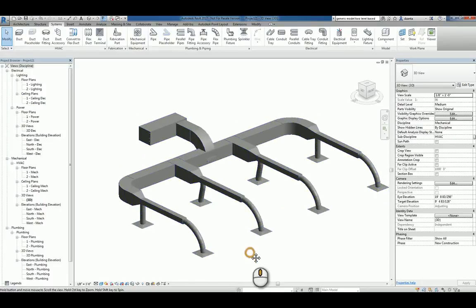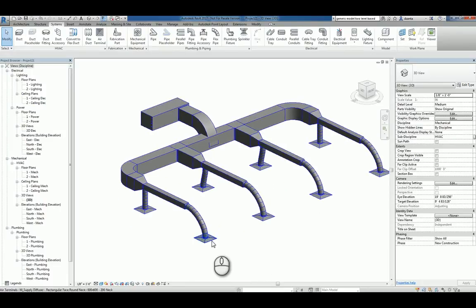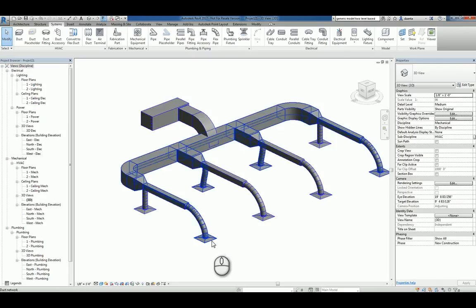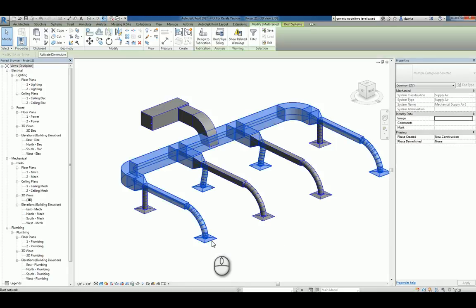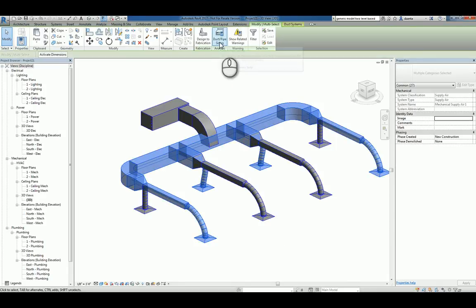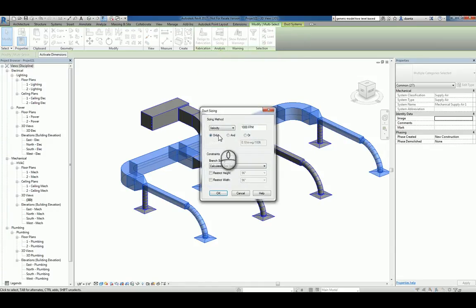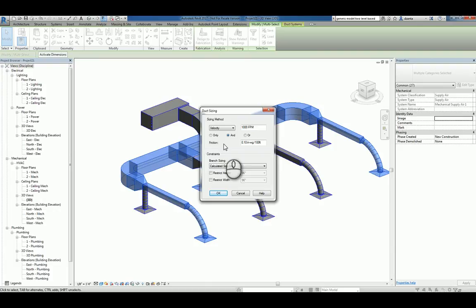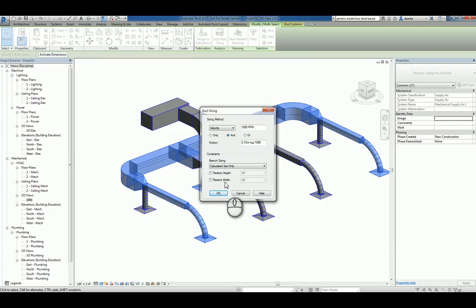Lastly, if you need to, you can use the Tab key to highlight the entire system. And do things like duct pipe sizing and make adjustments for whether the sizing is based upon velocity and or friction or a combination of the two. And you can also restrict the height and restrict the width if you need to as well.